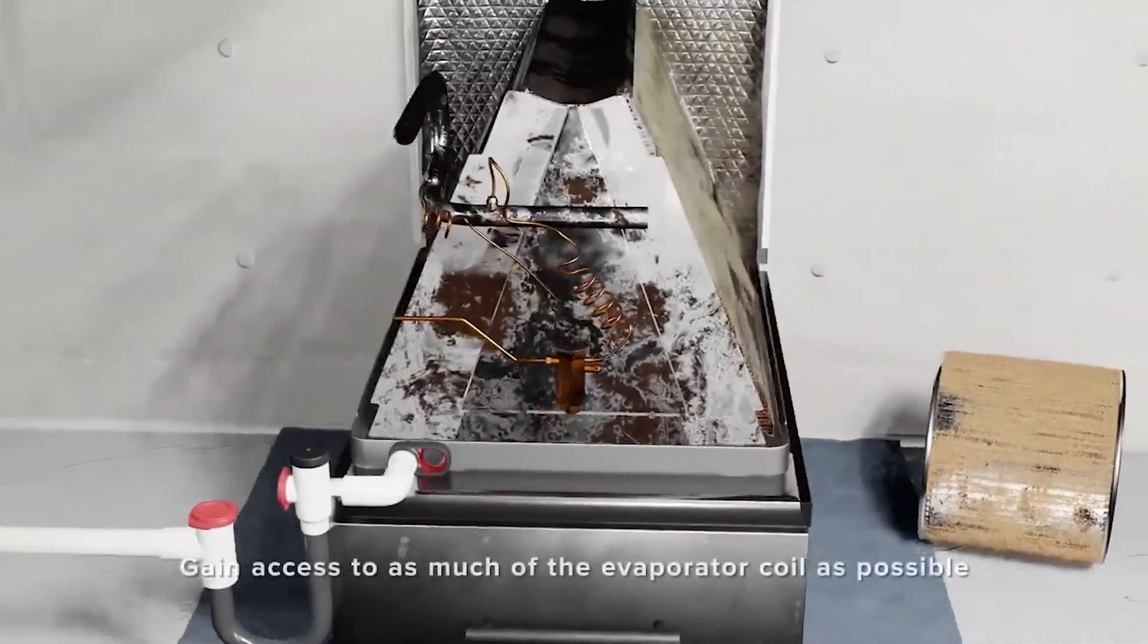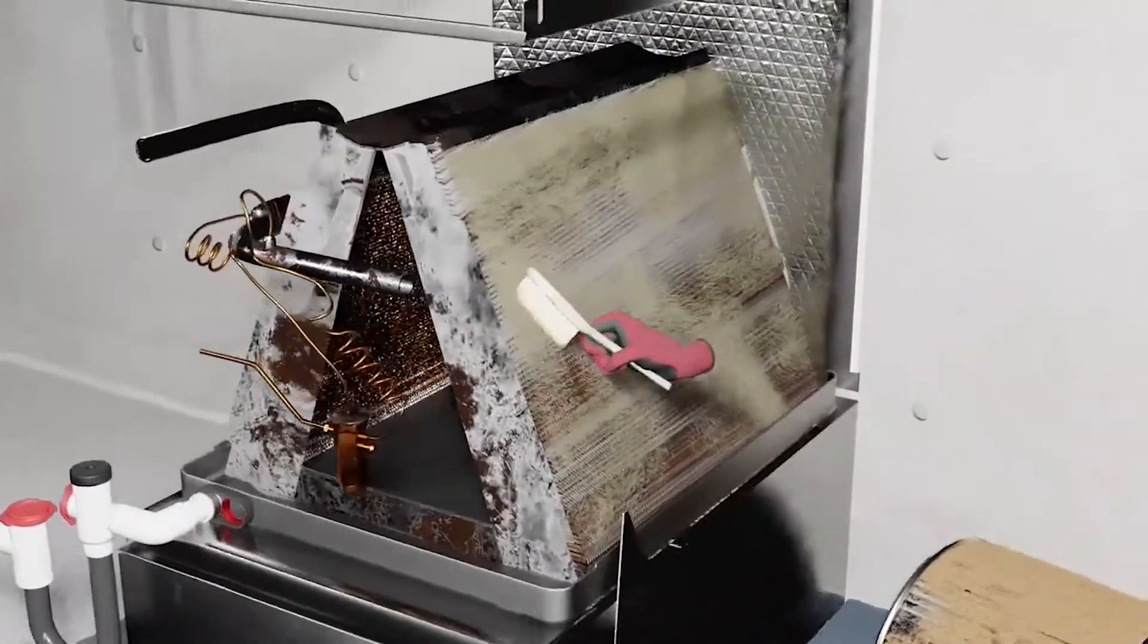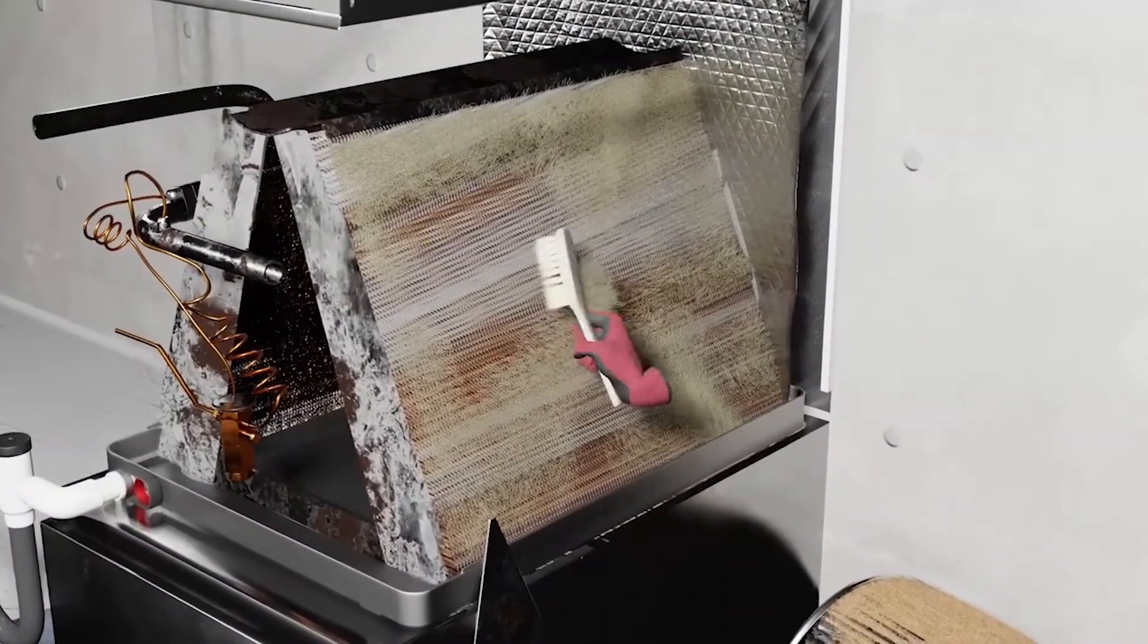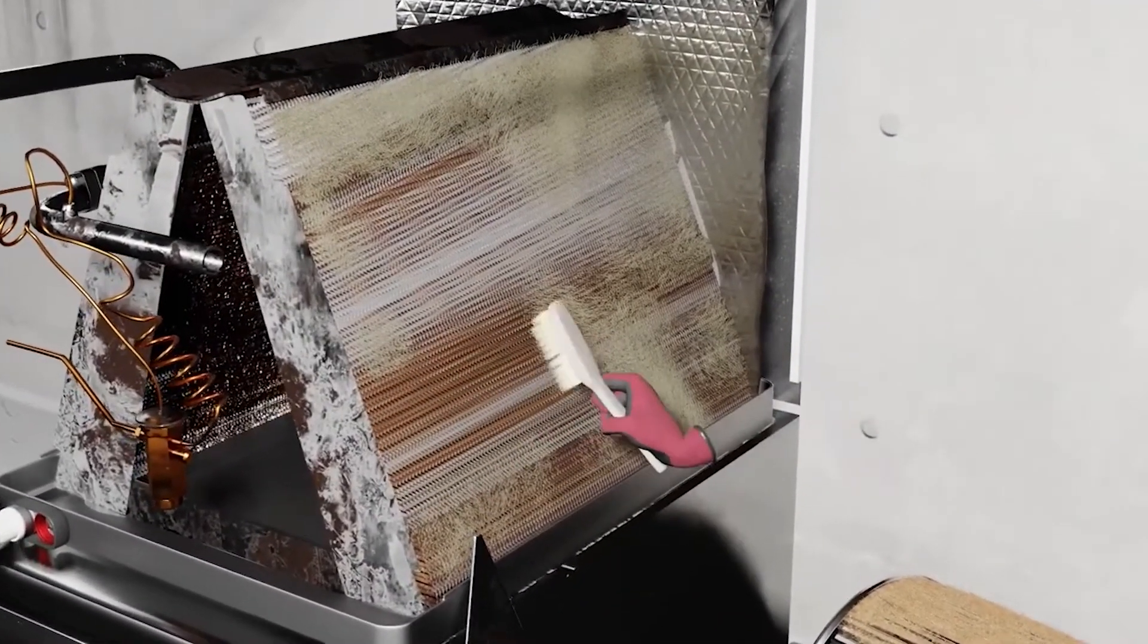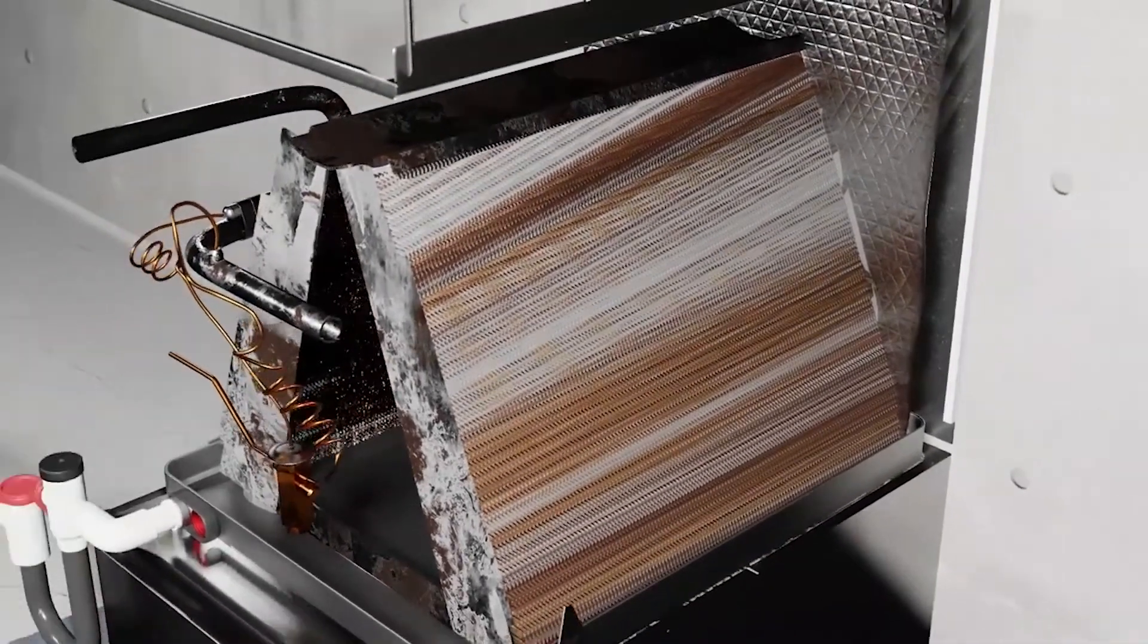In some cases, you can remove the triangular panel at the front of the coil to access the underside. In other cases, you may be able to gain access from underneath. We recommend using a soft bristle brush to clean as much of the solid debris as possible before beginning with chemical cleaners.